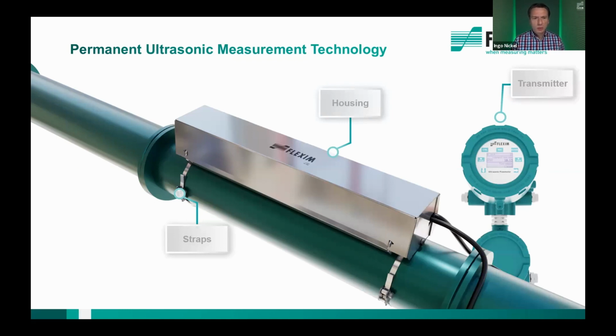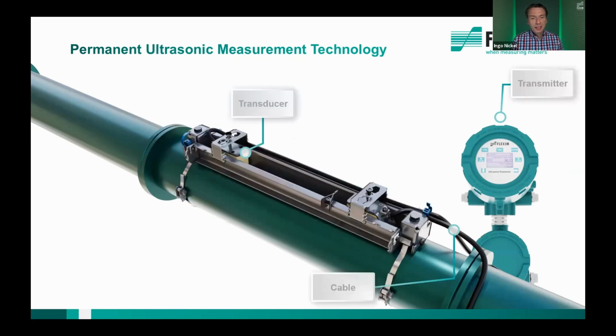And if we take a deeper look into this housing, then you see how the two transducers are mounted on the pipe. They are fixed with coupling pads mounted on the pipe. It's a very robust fixation, and without any risk of moving of the transducers. It's a very robust mounting solution.